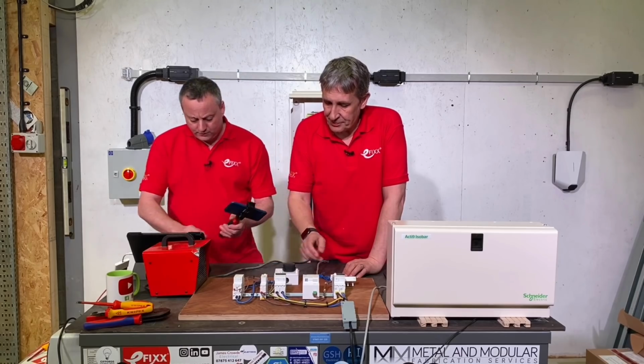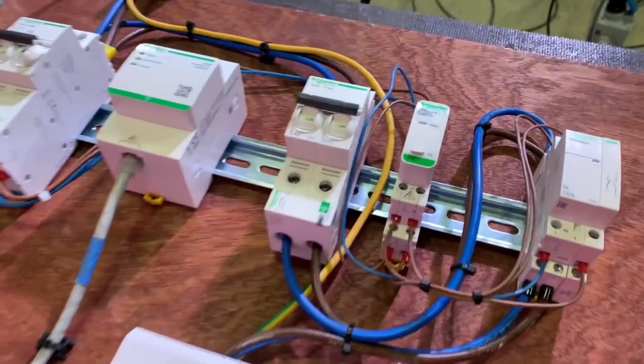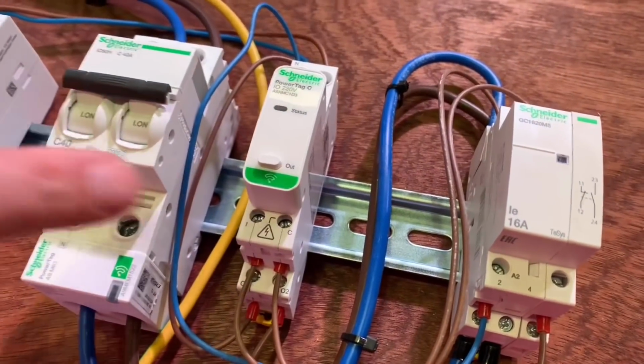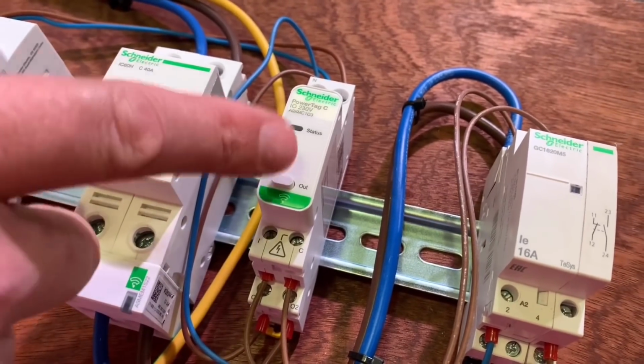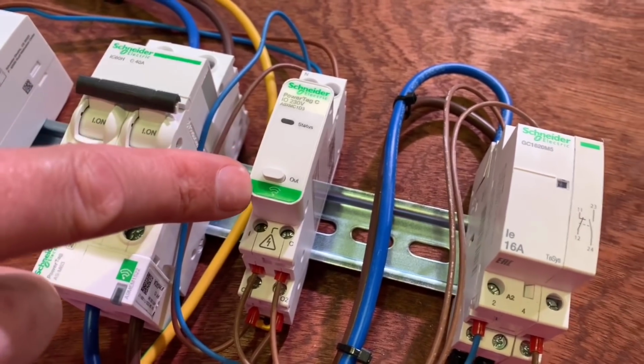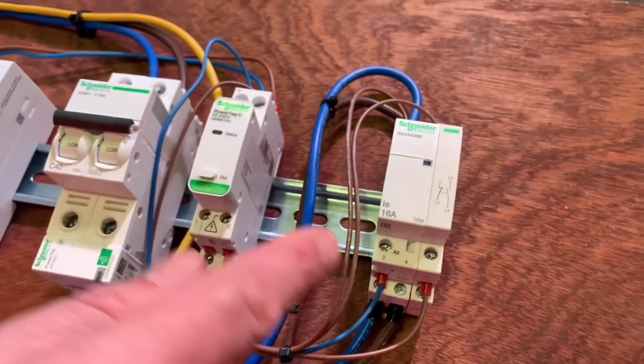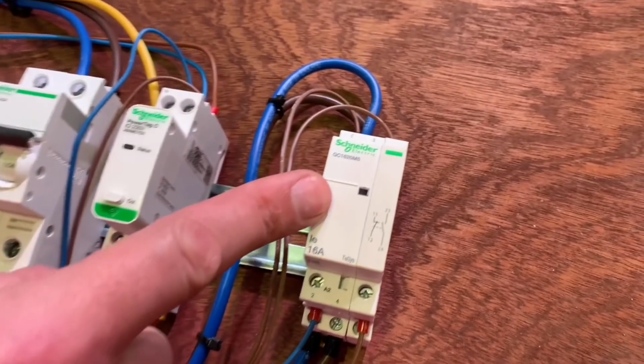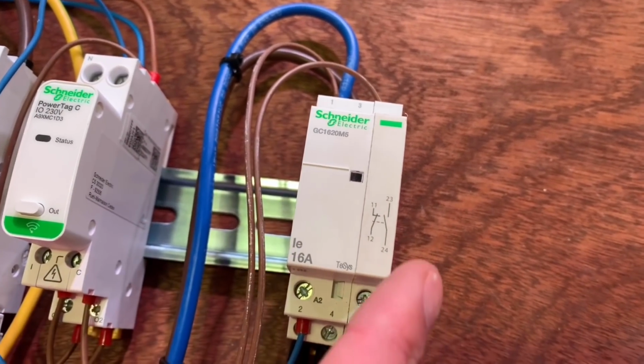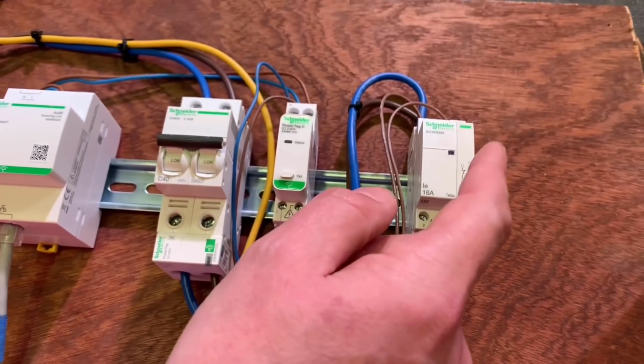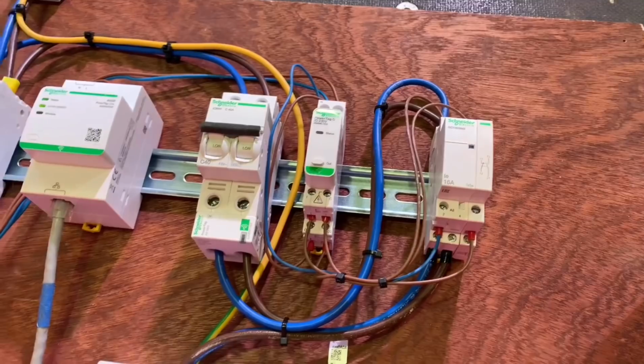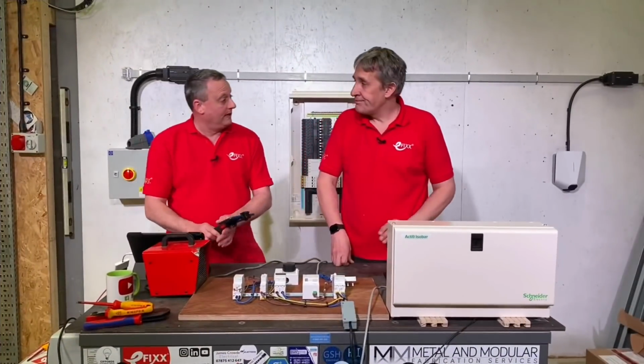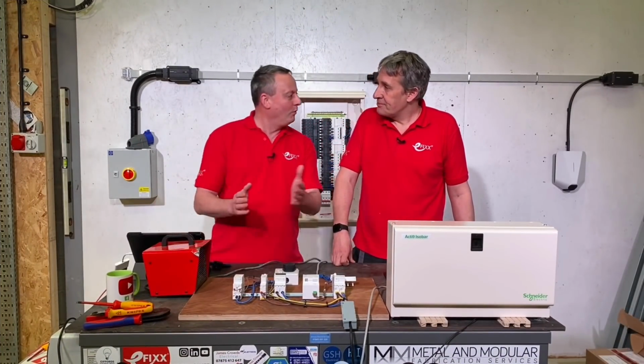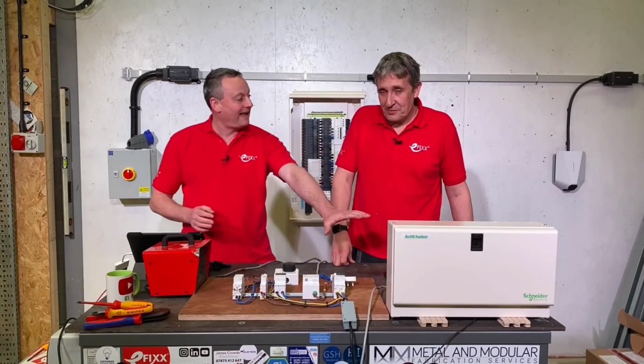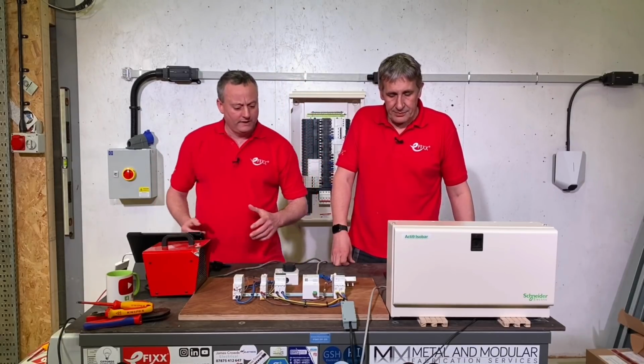Let's have a closer look at those, because I think you can activate them from here. Yes, you can — I could switch the load on and off using this button here, but even this we can configure, we'll look at that in a little while. So this is an output module, and I've hooked this up to a contactor here, and it's also got an auxiliary contact feeding back into the system so we know the contacts have actually closed. Wow, it looks remarkably good, and there's a little bit back here we're going to have a look at as well later in the video.